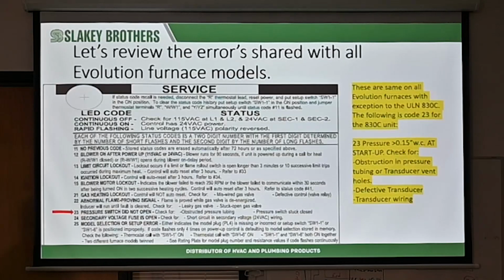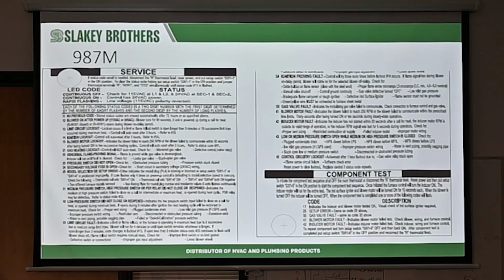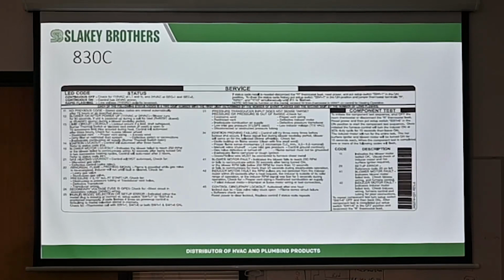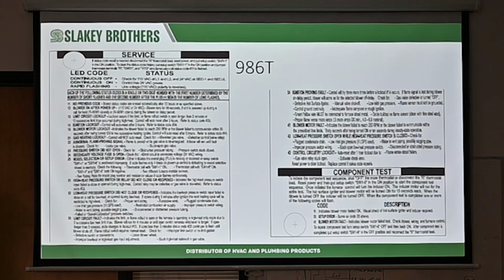Okay, where are we going on? Each one has its own diagnostic. So you could go to the Connex controller, or you can go directly to the furnace, and you're going to look at and see what it's flashing. All of them read the exact same way when you're looking at the error code. Each status code is a 2-digit number. The first number is by the short flashes, and the second number is the long flashes. Okay? There's still, with trying to get done here in time, there's a lot. I mean, you can see just even the 987M, there's a lot we can go over.